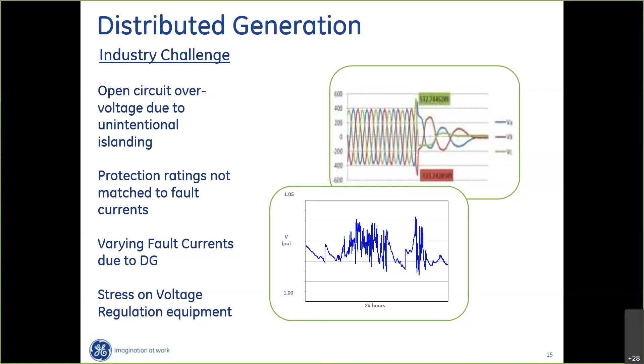Next, we have varying fault currents due to the distributed generation. That load side contribution is not constant, it varies because of the intermittency of the distributed generation. The sun isn't shining all the time, the wind's not blowing all the time. So how do we set the protection relays? What's the proper settings with a significant amount of load side contribution? And I'll talk more about the stress on the voltage regulation equipment.